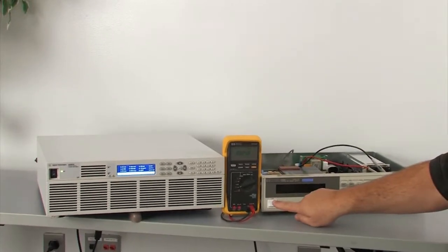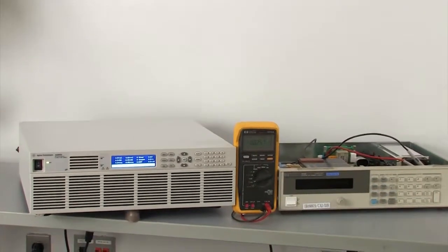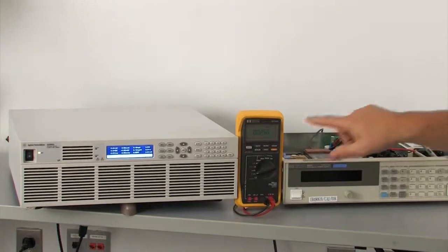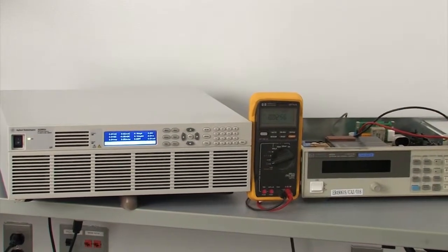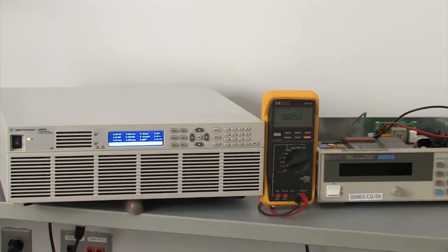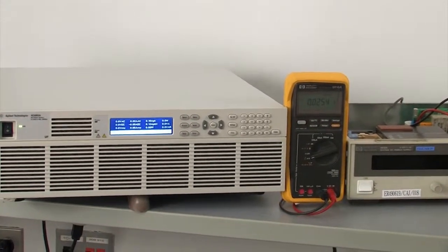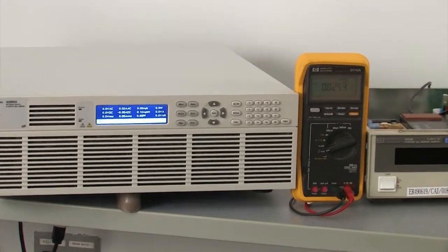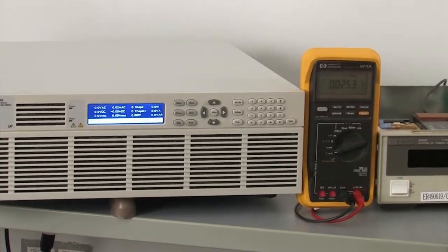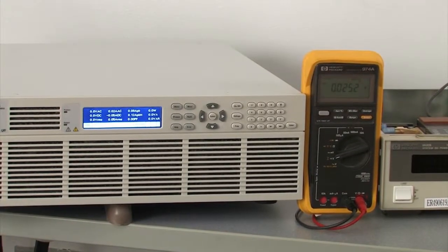I've already turned on the power switch for the power supply. The DC caps inside the unit are fully discharged because you're going to get the worst case inrush when the capacitors are at their lowest voltage, essentially zero.